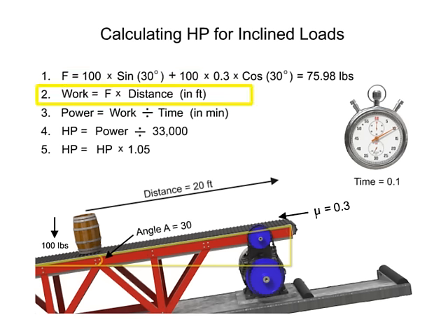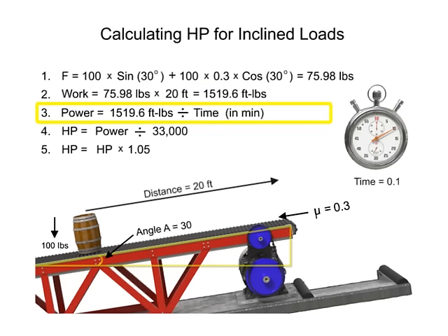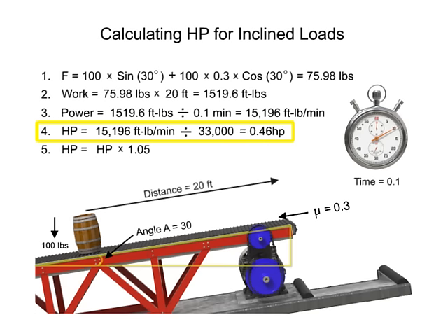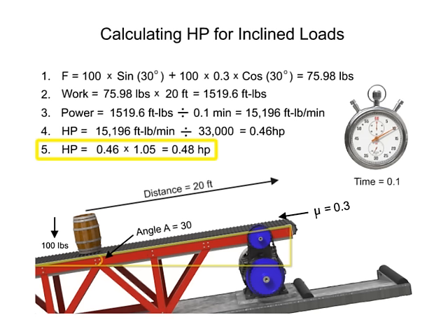Then, determine the amount of work required by multiplying the force by the distance: 75.98 pounds × 20 feet = 1,519.6 foot-pounds. Next, calculate the power by dividing the work by the time: 1,519.6 ÷ 0.1 minutes = 15,196 foot-pounds per minute. Convert to horsepower by dividing by 33,000, yielding 0.46 horsepower. Finally, add 5% to compensate for estimated friction losses, giving a final result of 0.48 horsepower. With this result, system designers can ensure the right size motor is available to operate the conveyor on an incline.